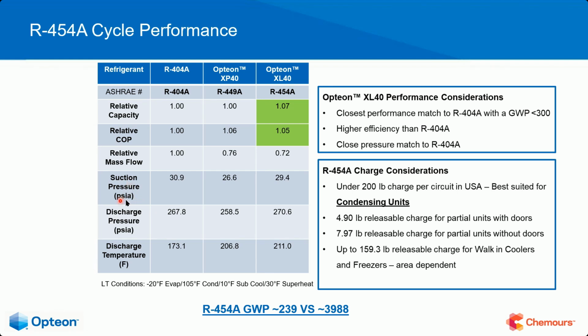Suction pressures. Now this is PSIA. Don't let that confuse you. We always use PSIG. PSIA, simply put, is your gauge pressure, PSIG, with atmospheric pressure or standard atmospheric pressure added to it, which we typically say is what? 14.7. Some people round it up to 15. You're simply adding that 15 to your gauge pressure, whatever you're seeing on your gauges, whether they're digital or the old mercury gauges. All right. So with that said, suction is 30.9 in 404A on the low side. Suction for 449A will be 26.6. And then on the new equipment will be 29.4. So not a big difference there.